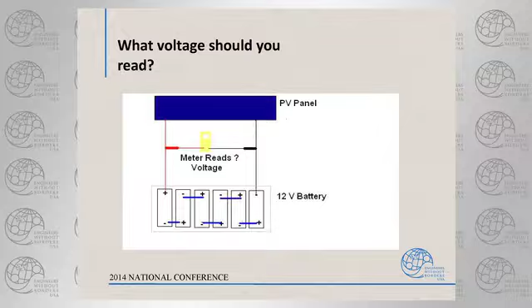Next. All right, we've got the same situation here, but in this case, internal in there, our series connection had a corrosion because the connections between the cells are made out of lead that's poured, and when that molten lead is poured, it crystallizes. And sometimes you get what's called intergranular corrosion, or you just get massive corrosion, and the straps between the cells break down. Now I've got an open right there.